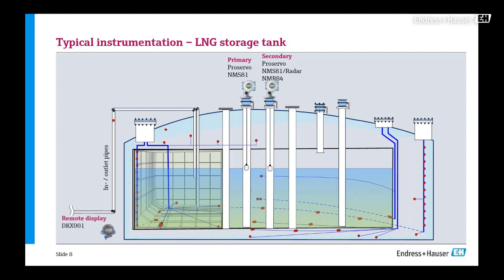Then we talk about the remote display. Imagine a 50 meter tank - very few people would like to climb it, so they utilize a remote display at the bottom of the tank. One of the biggest advantages of this remote display is that it is a clone of the display on top of your gauge. Since it's a clone, you can also do parameterization at the bottom of the tank, and do a quick check when there is an alarm. That is very unique for this remote display.